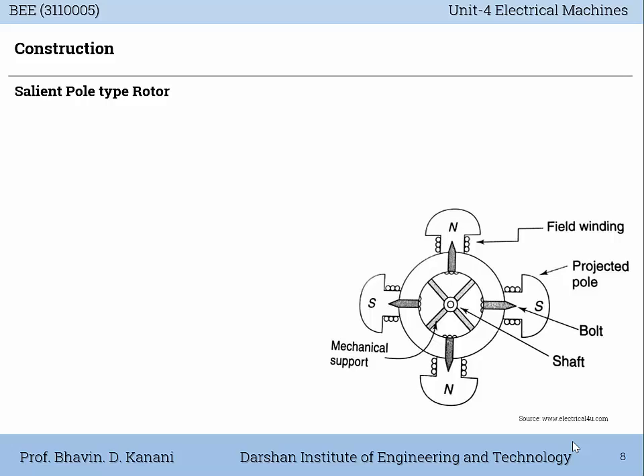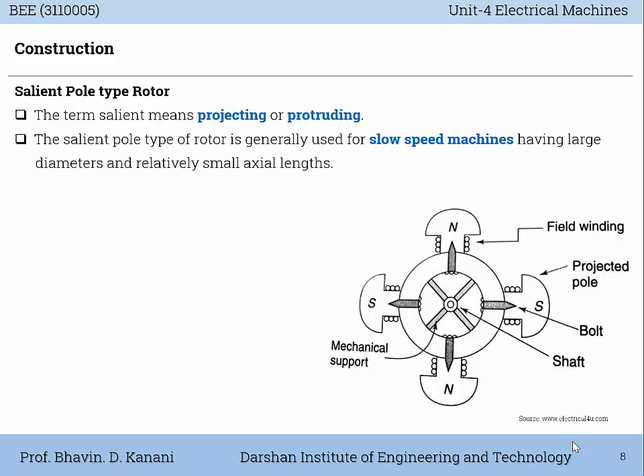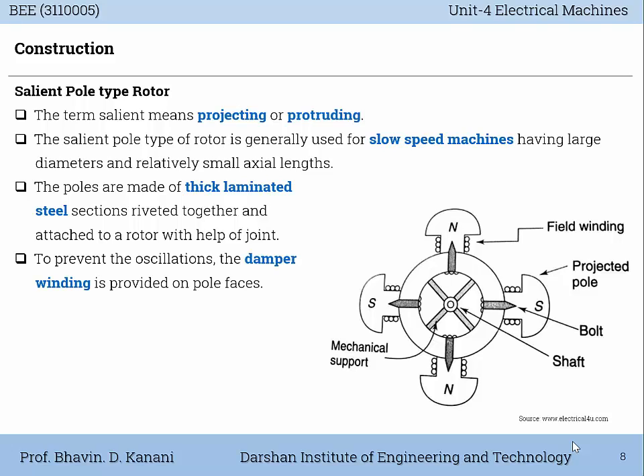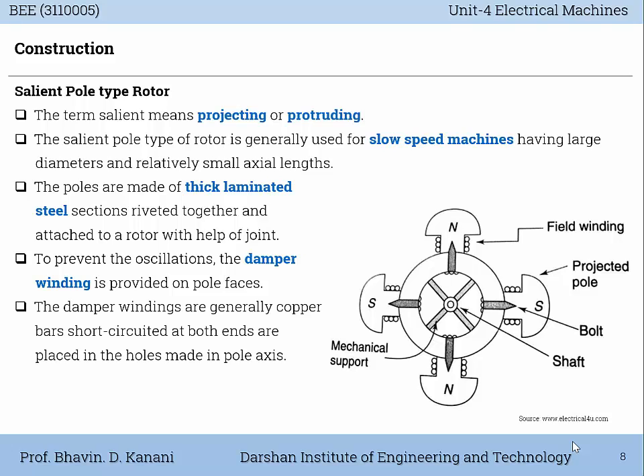Now the construction of the salient pole type rotor is very well explained by this diagram. The term salient means projecting or protruding. The salient pole type of rotor is generally used for slow speed machines having large diameters and relatively small axial lengths. The poles are made of thick laminated steel sections riveted together and attached to a rotor with the help of a joint. To prevent oscillations, the damper winding is provided on the pole faces. The damper windings are generally copper bars short circuited at both ends, placed in holes made in the pole axis.